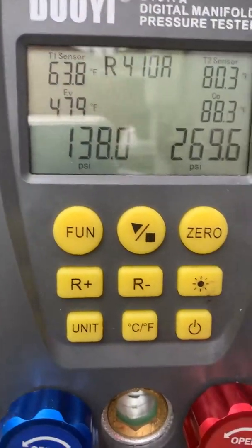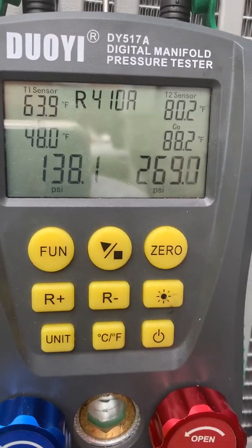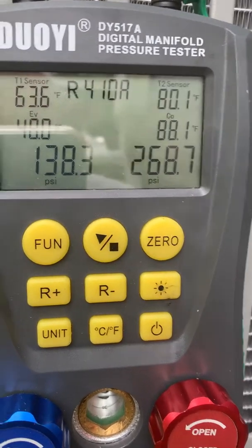I've got a temperature of 63.6 coming back out of my upstairs unit. I think this is where I'm going to end it. I could have put more in - I would have felt comfortable going right around 272 to 278, somewhere in that zone. But I'm at 270.